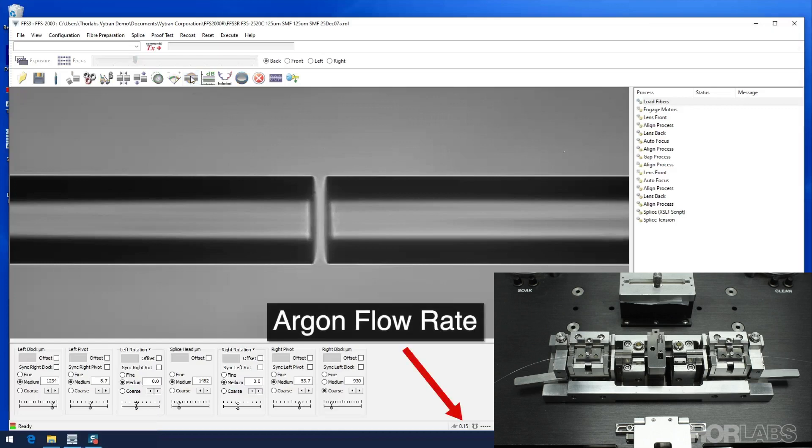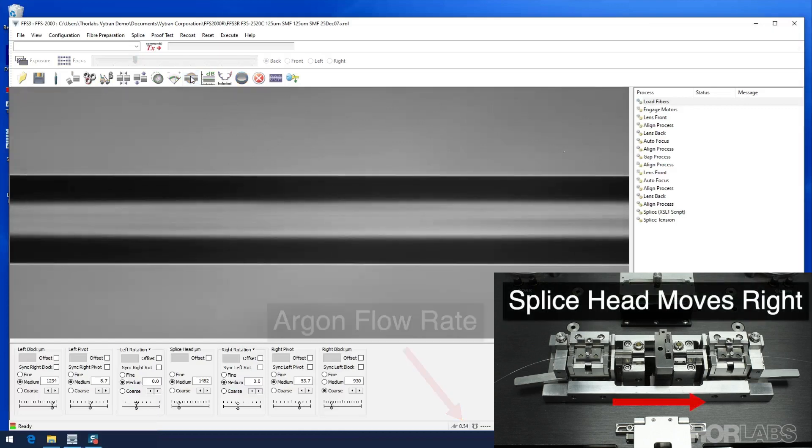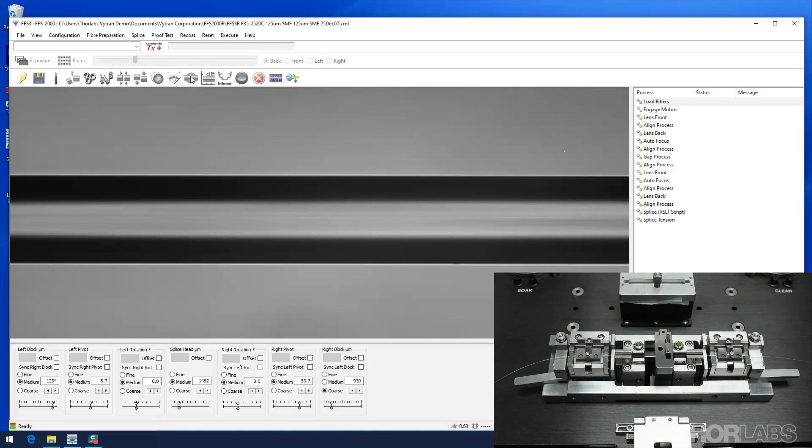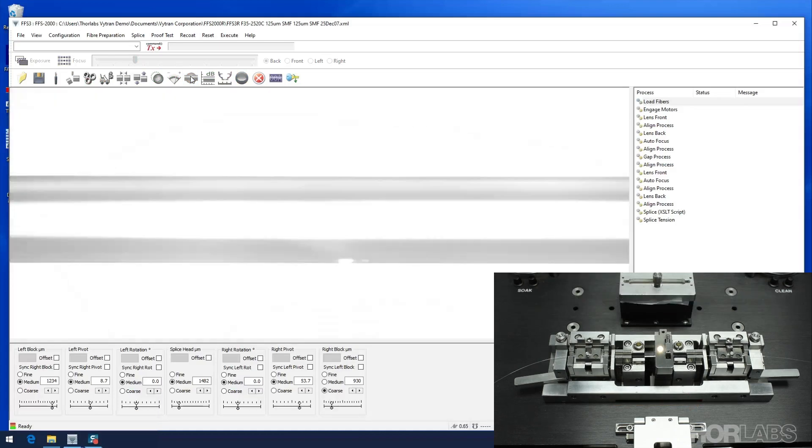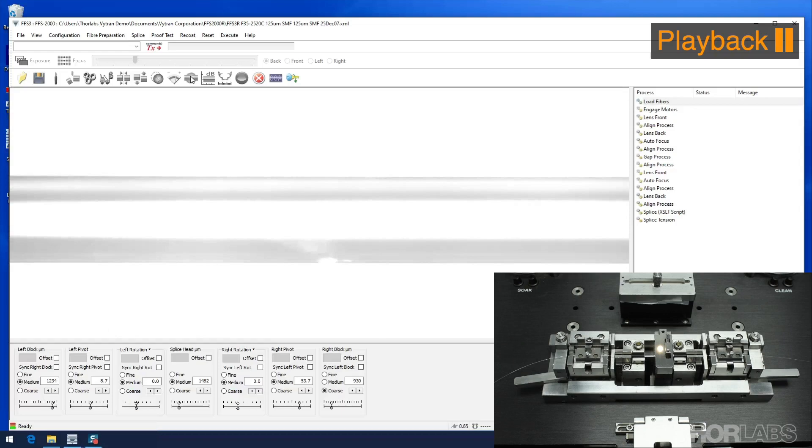The argon rate will also increase from the background flow rate to the splice flow rate. The filament will rise to its operating temperature and after the hot push delay time, the right fiber holding block will move forward by the hot push distance.